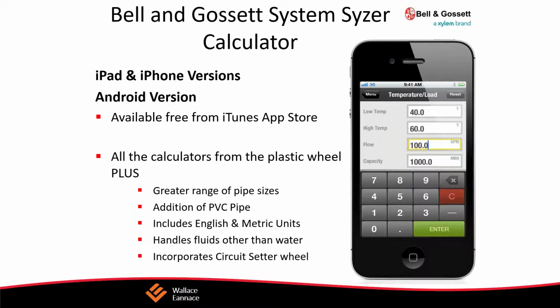And as you can see from the previous discussion, with a 20-degree delta T, 1.5 GPM correlates to 15,000 BTUs, 4 GPM to 40,000, 8 GPM to 80,000, 14 GPM to 140,000, 20 GPM to 200,000, and 45 GPM to 450,000. Basically, whatever the GPM is, multiply it by 10,000, and that'll give you the BTUs delivered.